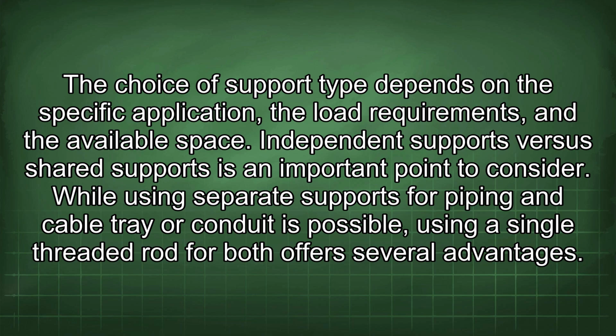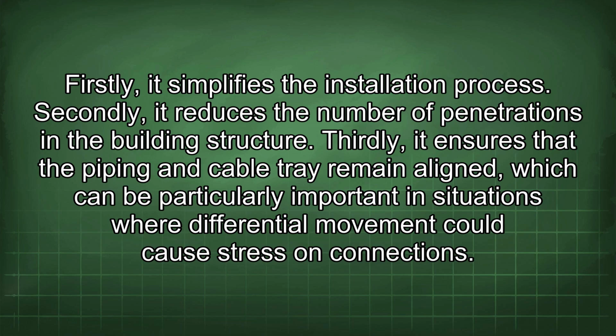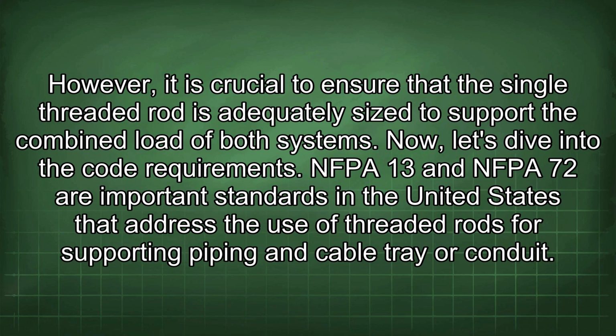Independent supports versus shared supports is an important point to consider. While using separate supports for piping and cable tray or conduit is possible, using a single threaded rod for both offers several advantages. Firstly, it simplifies the installation process. Secondly, it reduces the number of penetrations in the building structure. Thirdly, it ensures that the piping and cable tray remain aligned, which can be particularly important in situations where differential movement could cause stress on connections. However, it is crucial to ensure that the single threaded rod is adequately sized to support the combined load of both systems. Now let's dive into the code requirements.